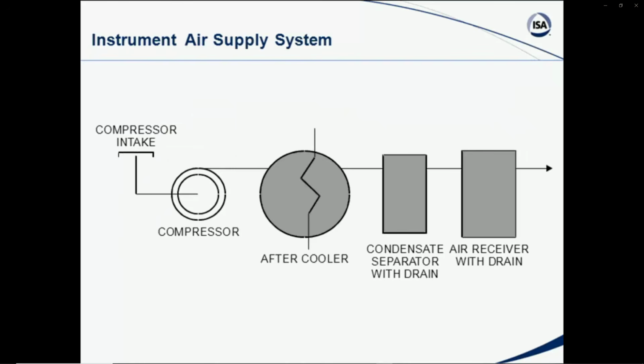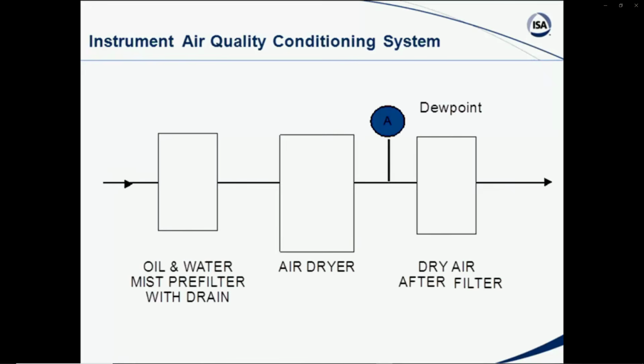For instance, here's a sort of a typical instrument air supply system that you might see in certain circumstances where the compressor is used, but we also go through a series of aftercoolers, maybe a separator, air receiver with a drain. We're trying to get liquid out of the air. We're trying to begin to cool that down and get it to a situation that we'll have a dry air.